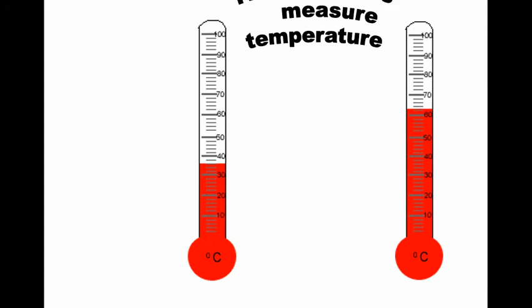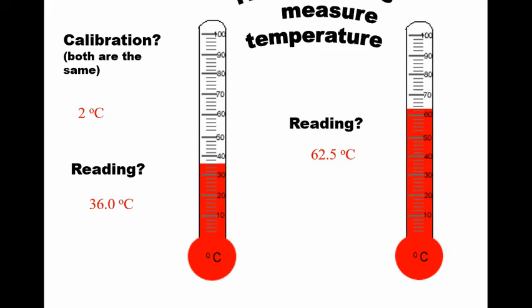Thermometers have a typical calibration of 2 degrees Celsius. So you have to be careful that you recognize that each line is worth 2 degrees. So it's 3 lines up. That doesn't make it 33. It makes it 36. And then I'll add an estimated digit of 0.0 because I think it's right on the line. I can also think it's halfway through the line, and this one would have a reading of 62.5 degrees Celsius.